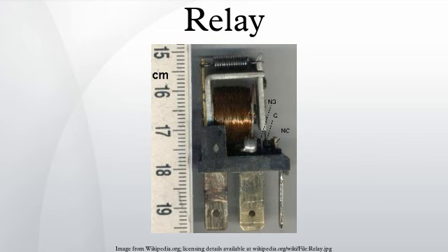Continuous current ratings for common contactors range from 10 amps to several hundred amps. High current contacts are made with alloys containing silver. The unavoidable arcing causes the contacts to oxidize. However, silver oxide is still a good conductor. Contactors with overload protection devices are often used to start motors.